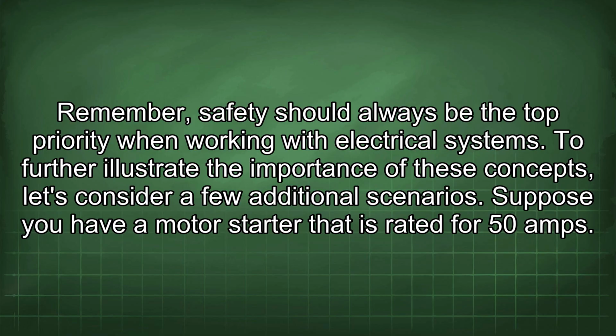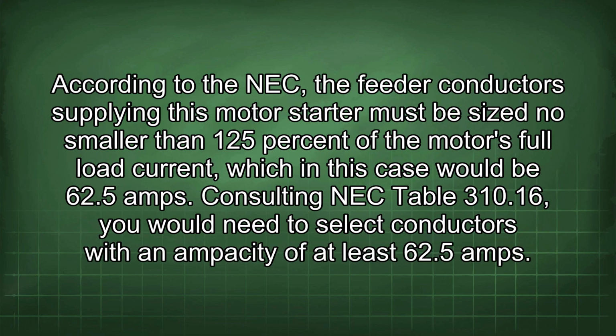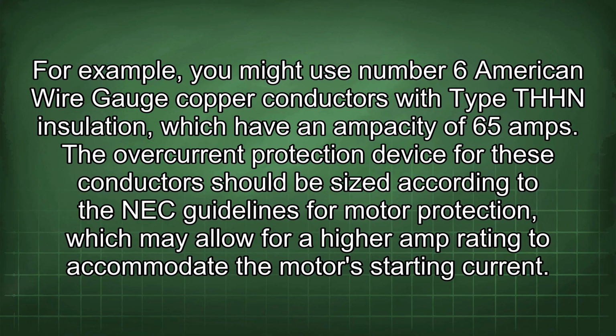Suppose you have a motor starter that is rated for 50 amps. According to the NEC, the feeder conductors supplying this motor starter must be sized no smaller than 125% of the motor's full load current, which in this case would be 62.5 amps. Consulting NEC Table 310.16, you would need to select conductors with an ampacity of at least 62.5 amps. For example, you might use number 6 American wire gauge copper conductors with type THHN insulation, which have an ampacity of 65 amps. The overcurrent protection device for these conductors should be sized according to the NEC guidelines for motor protection, which may allow for a higher amp rating to accommodate the motor's starting current.